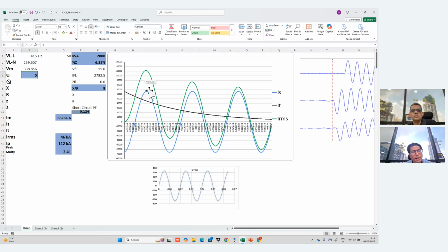Normally we see transformer capacity of 2000 kVA or 2500 kVA. At the maximum we can see transformer capacity up to 3200-something kVA, because the maximum breaker current I think is a 6300 ampere circuit breaker. So on the LV side, on a 415 volt system, the current is limited by the 6300 ampere breaker. I don't know whether any development has occurred recently, but to my knowledge 6300 ampere is the maximum breaker. That limits the capacity of the transformer basically.